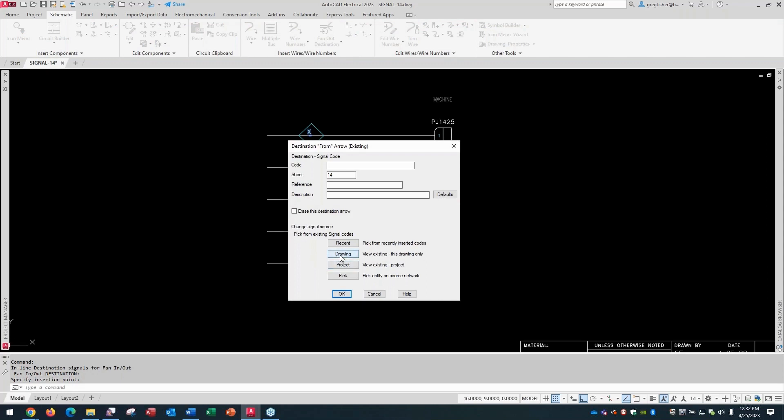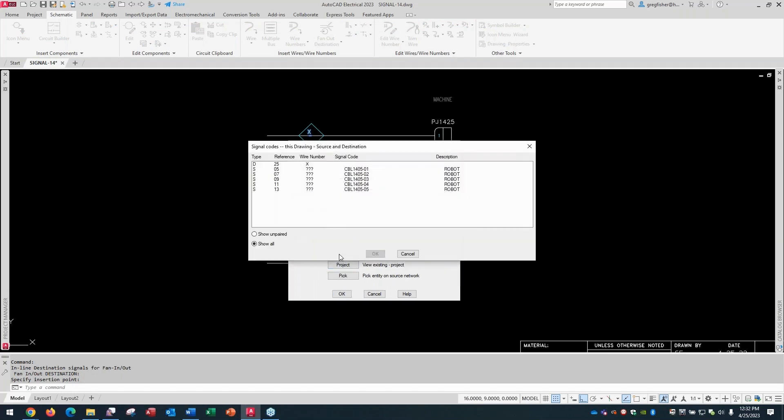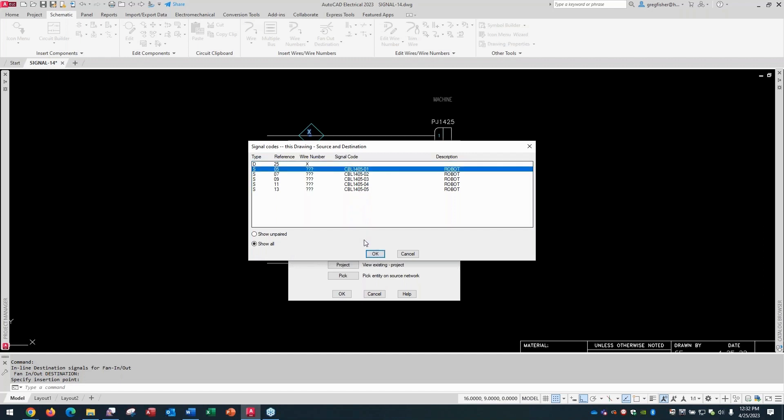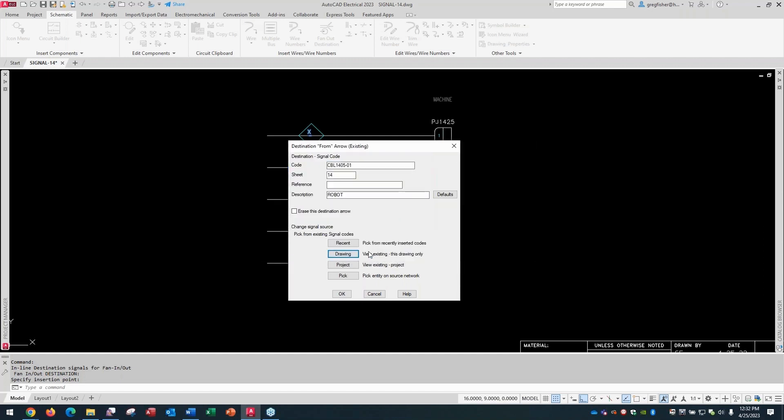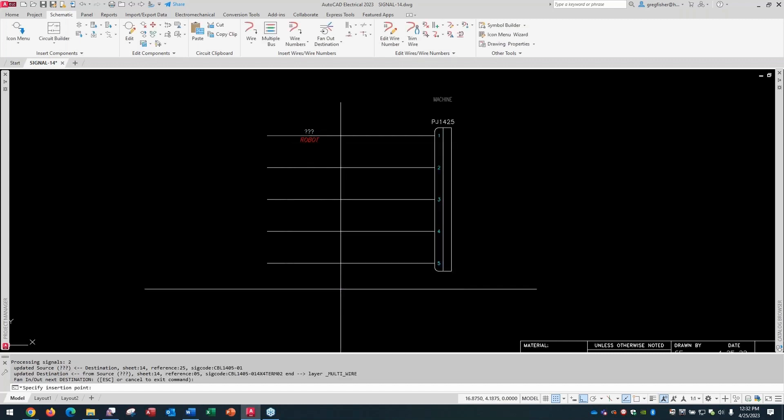And then I'm going to go to the drawing button to pick the code. This is very best practice, if you will, here. You're a lot better off, and this holds true for regular source and destination, you're always better off picking the destination from a list. Because if you make a typo, it simply won't work. If you make a typo, the code is different from the source. They're not going to be linked together. It's not going to know that it's the same wire. So I'll pick OK here on this one.